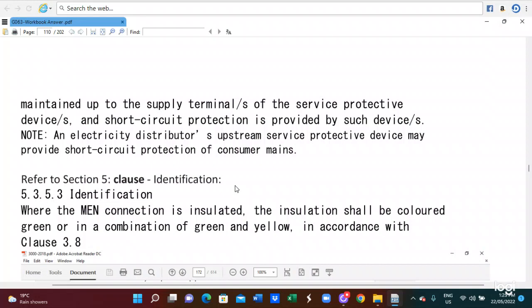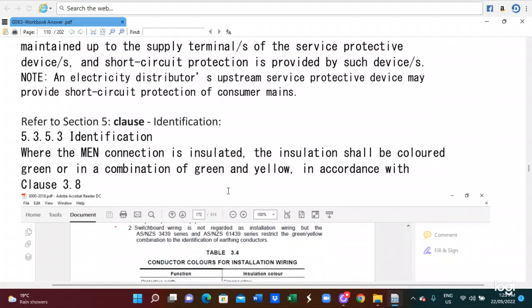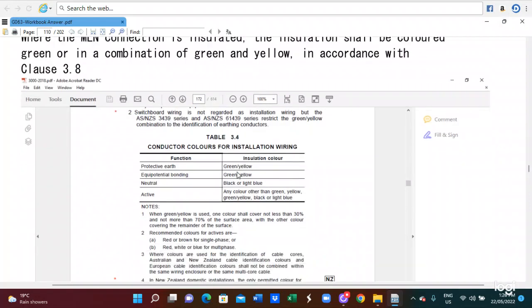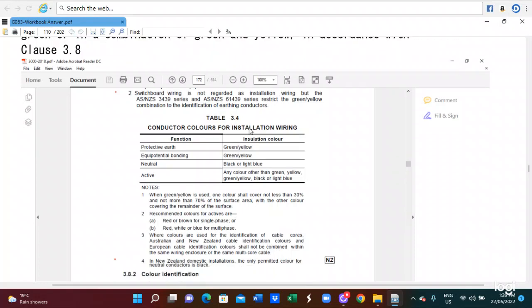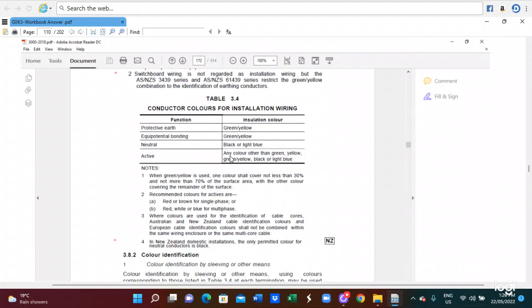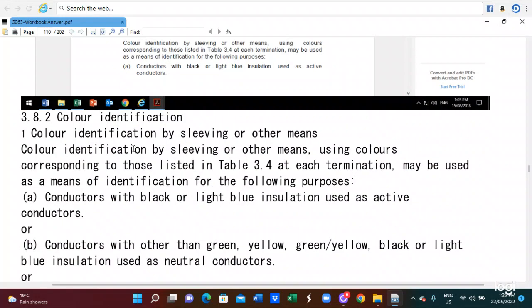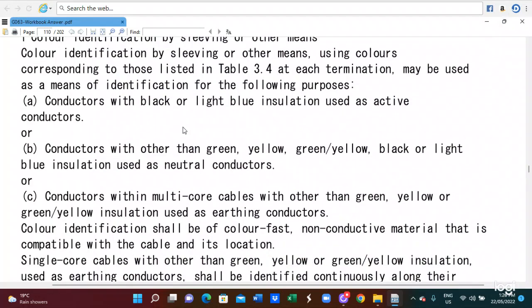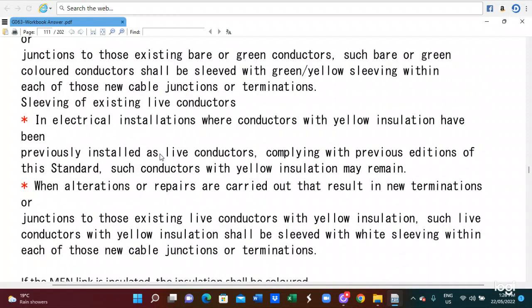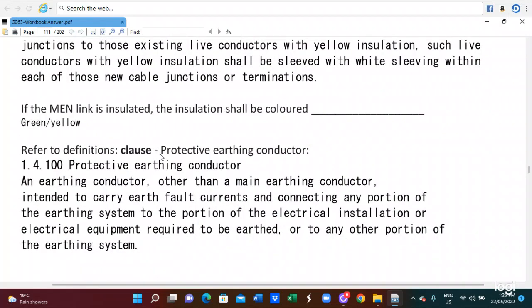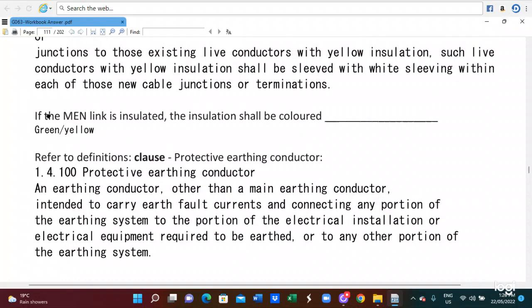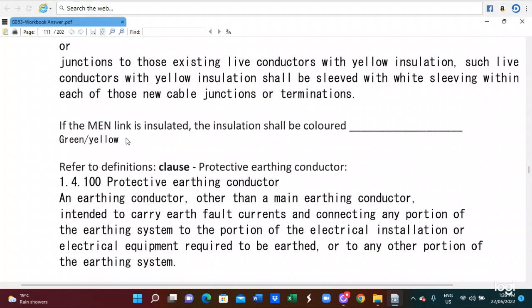And clause 5.3.5.3 mentions the identification. Where the bonding connection is insulated, the insulation shall be colored. So for this you have to read Table 3.4, conductor colors for installation wiring. Table 3.4 in the 3000 standard mentions the conductor colors for installation wiring. For no conductor color identification, you have to follow clause 3.8.2. So this is the color identification. They also say the earthing conductor, where insulated, shall have insulation colored green and yellow.